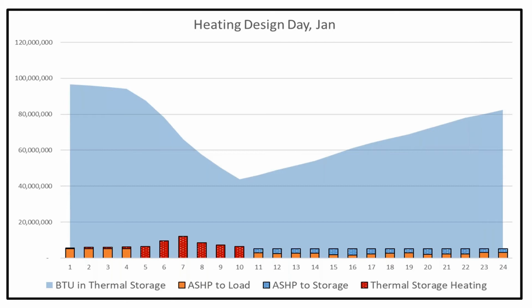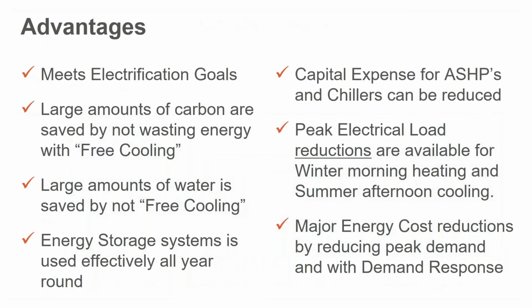Now, it's true, some of this energy might not be waste energy that you saved. And in this example on design day, we took that, but a heat pump running from, let's say, 0 up to an ice melt temperature of 45 is a very, very high COP heat pump. So your demand reduction is there, and it's dramatic, especially when the utility is going to be needing that demand reduction. And obviously, there's major energy cost savings by reducing the peak demand both in the summer and the winter, and saving the BTUs from the free cooling from the night before.